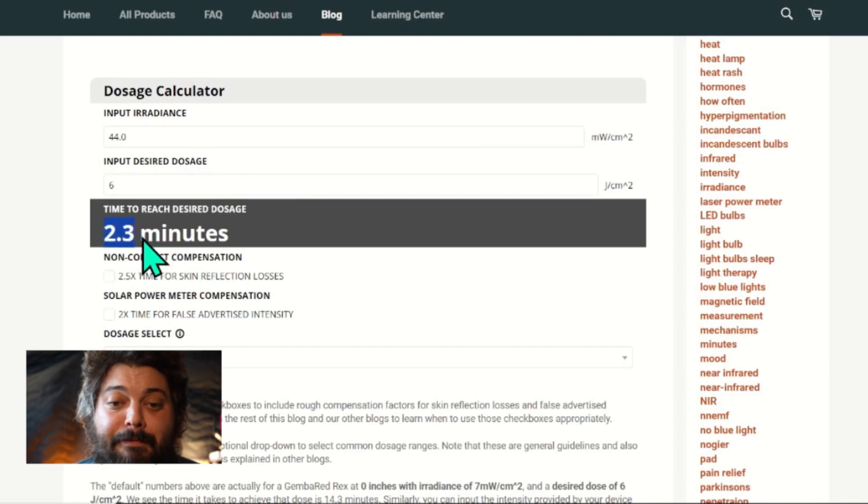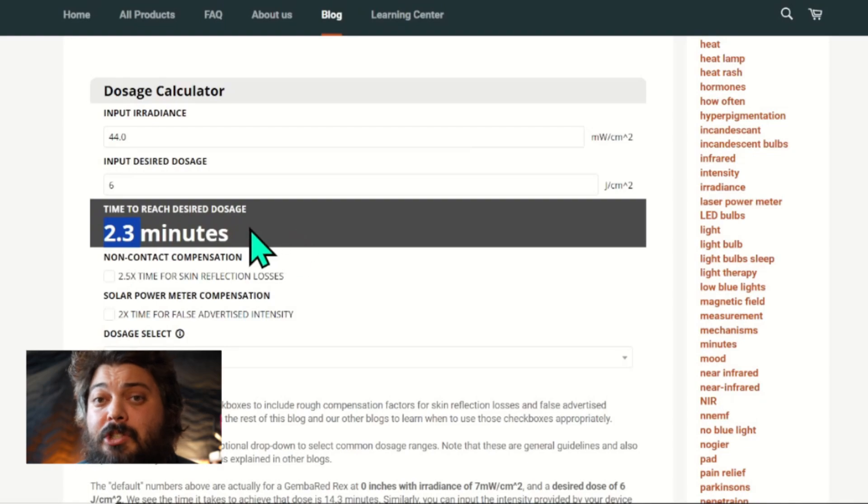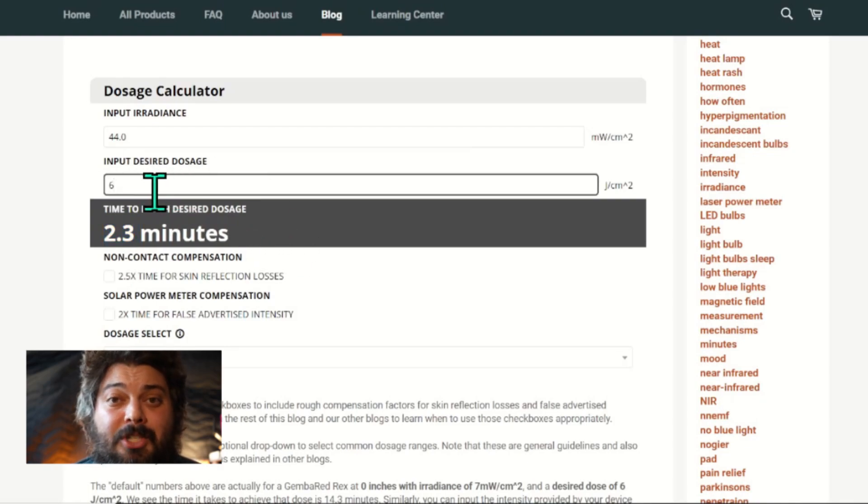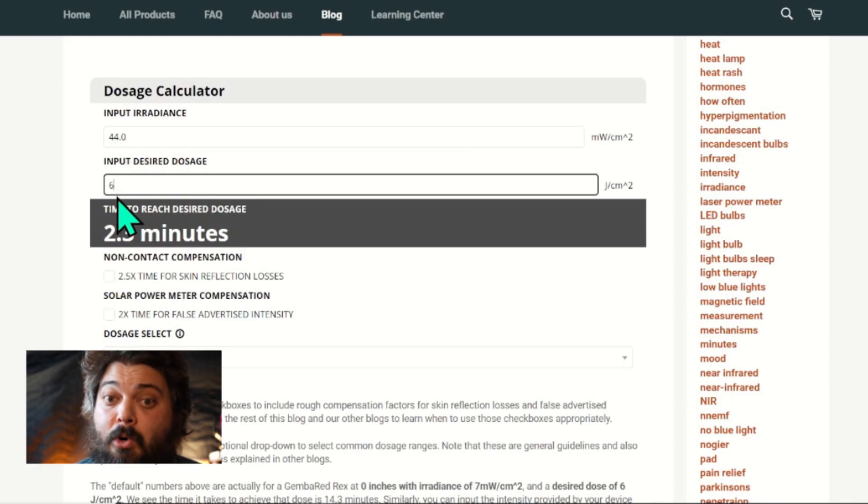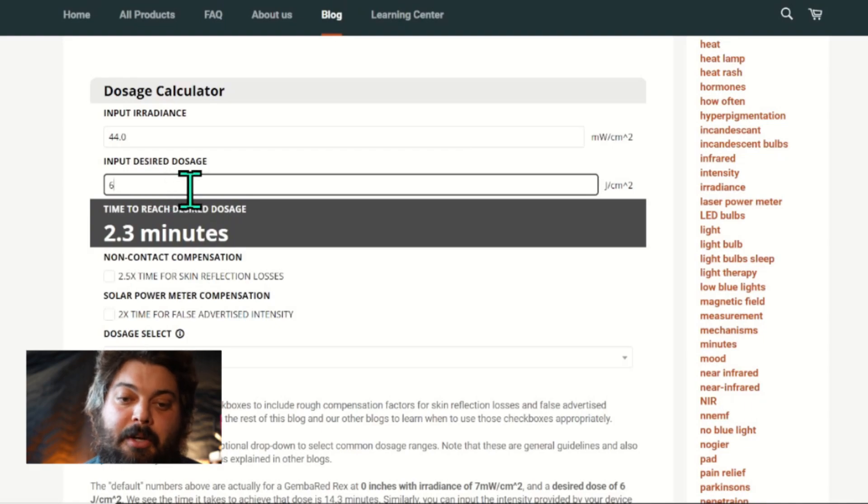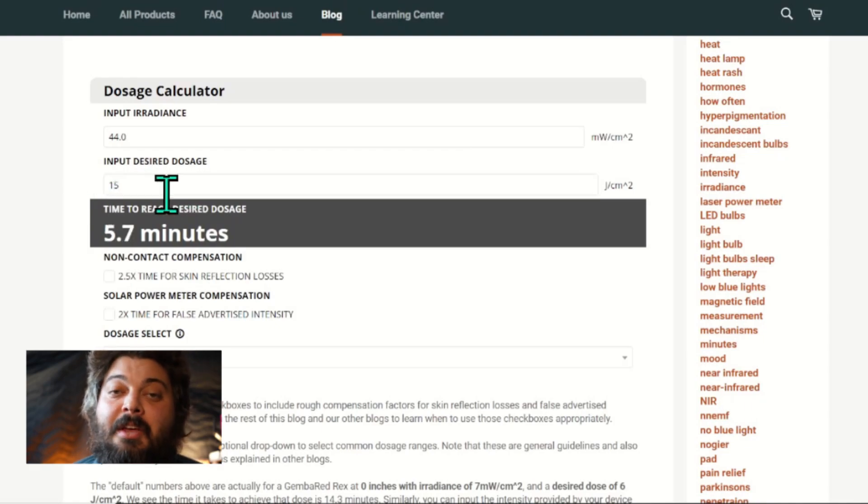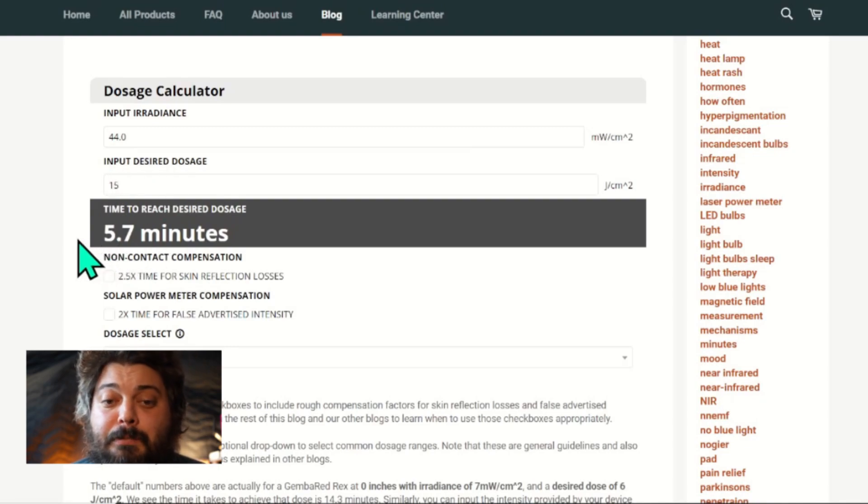That's a good dose, a little bit more superficial. It's a pretty good starting dose, I'd say, for deeper tissue just to see how you respond. But maybe you want a little bit more dose. So maybe let's put in 15 joules per centimeter squared, and then it automatically recalculates. You need 5.7 minutes to reach 15 joules per centimeter squared.